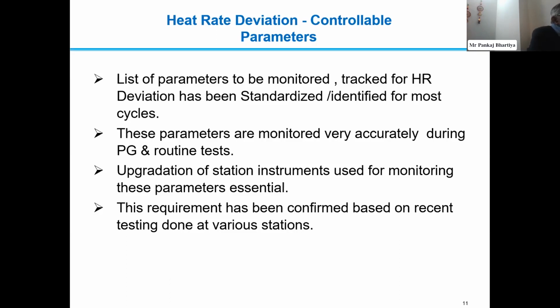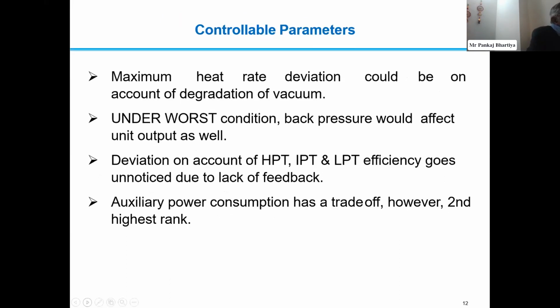Next, please. Yeah, the maximum heat rate deviation could be on account of degradation of vacuum, as has been discussed earlier also by the speaker. And under the worst conditions, the back pressure would affect unit output as well. So the deviation on account of HPT, IPT, LPT efficiencies goes unnoticed due to the lack of feedback. Auxiliary power consumption has a trade-off, and however, is second highest in rank. So we need to look at all these things. Next, please.